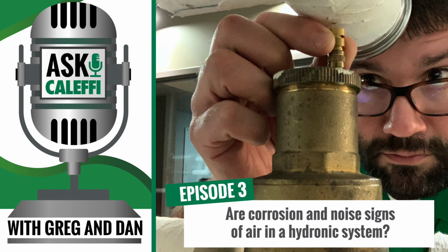And it usually is. The one advantage with that larger steel body is that it has that big drain port at the bottom so you can flush it off. You could actually pull the air vent assembly off the top, open the drain valve, and flush that coalescing mesh out if you had a really dirty system and you needed to clean that. You certainly could. The only thing you're not going to be able to fish out without taking the whole unit out of the piping is shop rags.